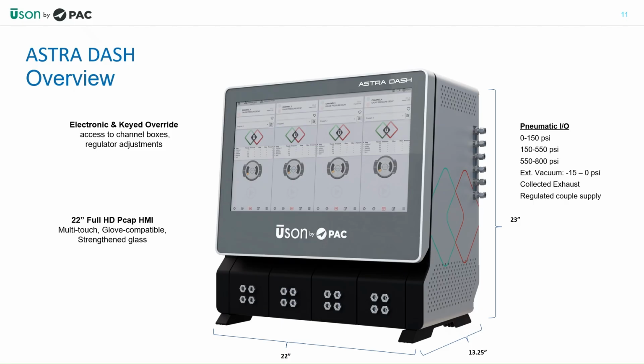The control core also handles all the pneumatic distribution for the channel boxes: standard, medium, and high pressure air or nitrogen distribution, an inlet for an external vacuum source, a collected exhaust line, and a dedicated line for regulated pneumatic couple supply air, all connected from the right side of the control core.